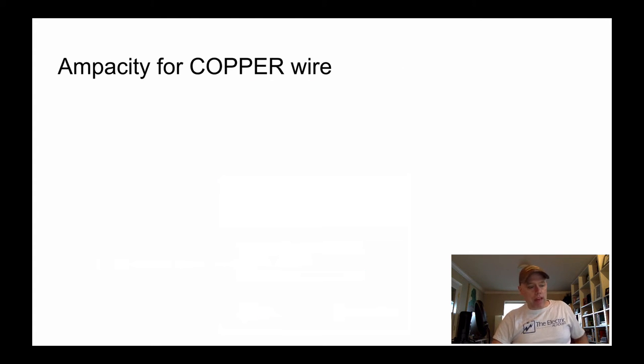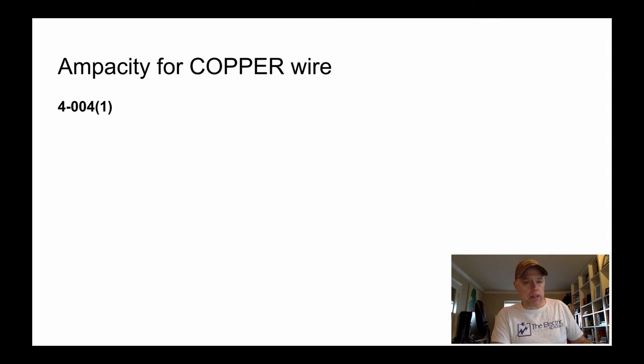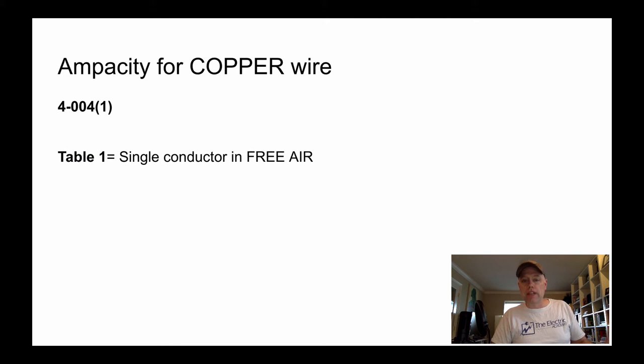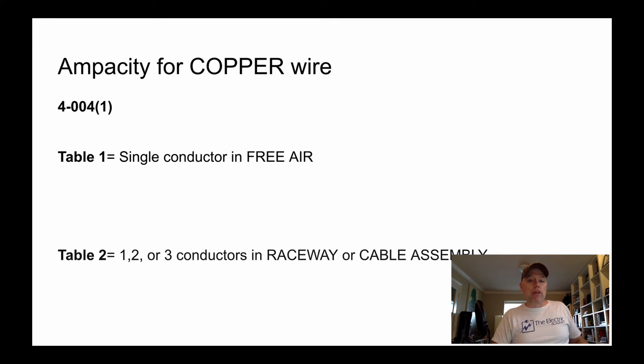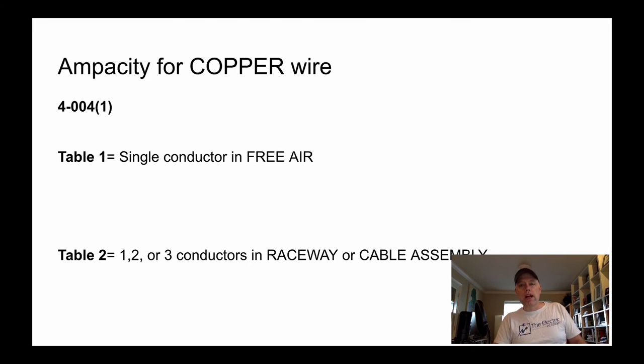The ampacity for copper wire is found in 4-004 subrule 1. For a single conductor in free air, we get our starting ampacities from table 1. If we're dealing with one, two, or three conductors in a raceway or cable assembly, we go to table 2 — and this is only for copper, not aluminum. Honestly, I spend probably 95% of my time starting in table 2, because I'm dealing with conductors going into a conduit or into a cable assembly like teck cable or multi-conductor teck.